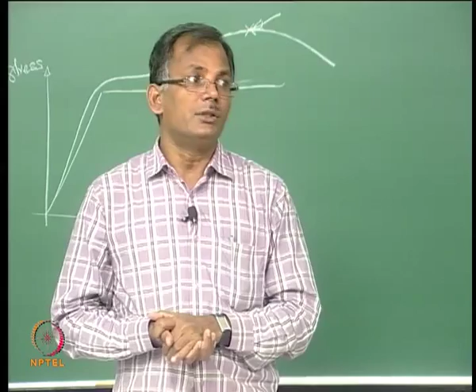For example, if you look at the subliming coatings, heat energy is absorbed by transforming solid to vapor. So, basically you have a very thin layer of this coating material. When it is affected by temperature, it actually vaporizes. The vapor forms the barrier between the fire and the steel. So, you have a cloud of this material, directly from solid to vapor, which does not permit the flame to go through into the structural surface. Subliming coatings are quite expensive, but the thickness of the coating may be just 5 mm, and when the temperature increases, it vaporizes and forms a thick cloud, which does not permit direct contact of the fire with the steel.